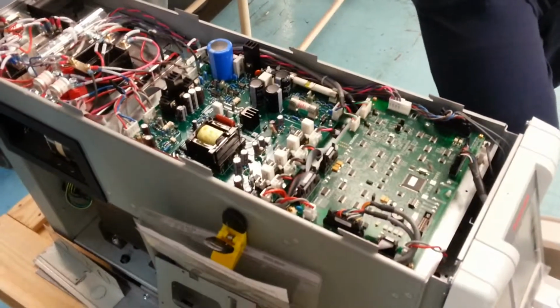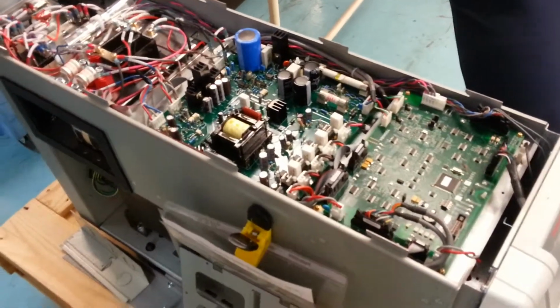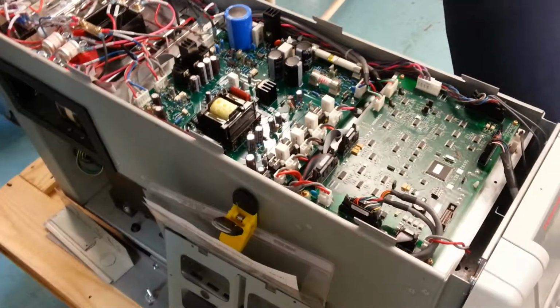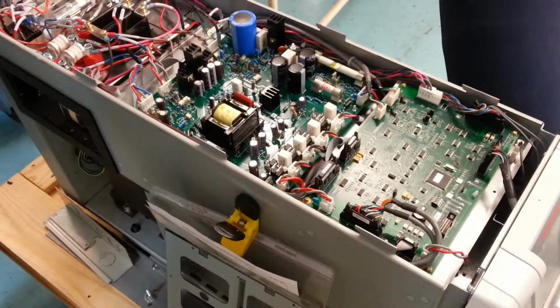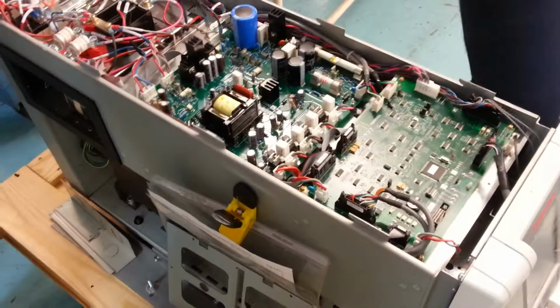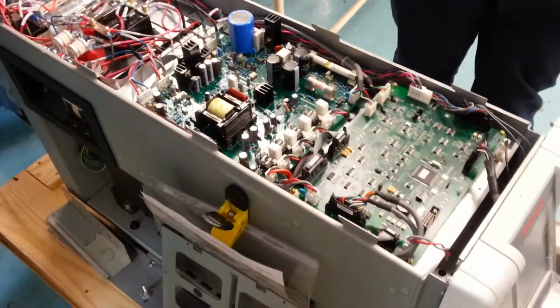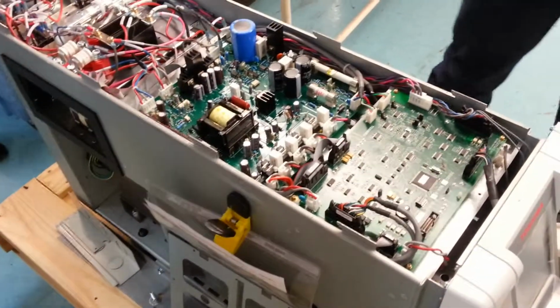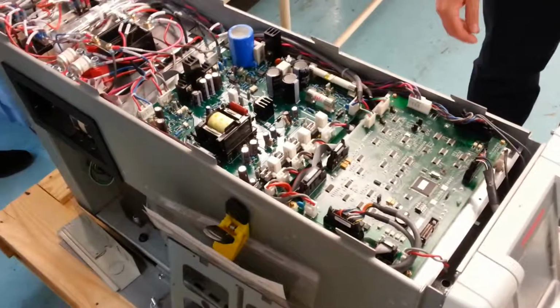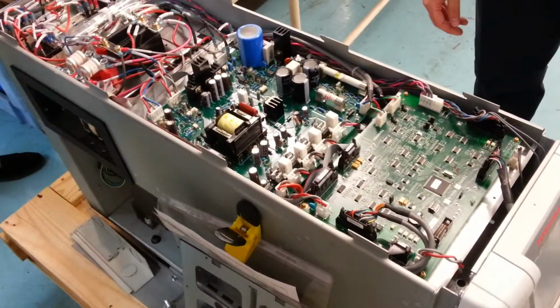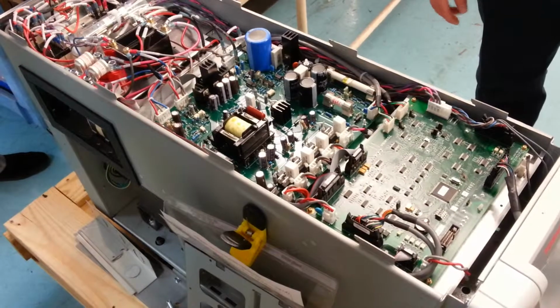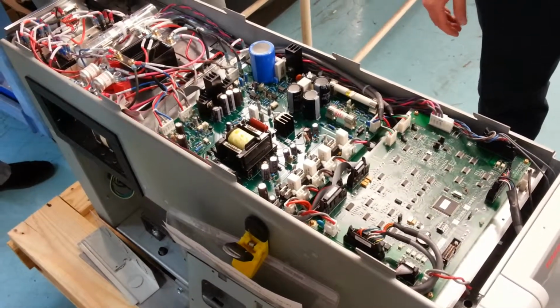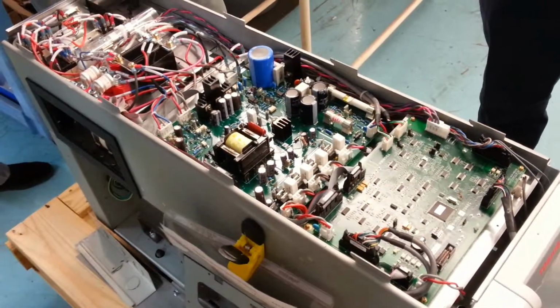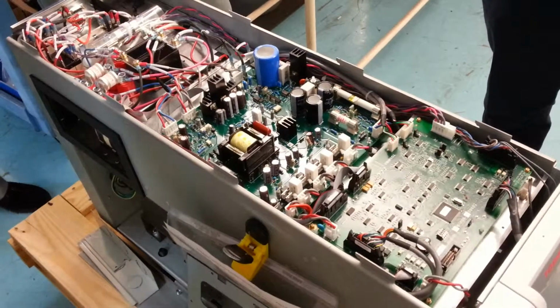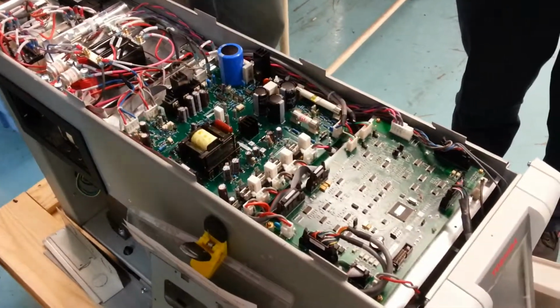But there's a point in the design of the board where the amount that can be drawn and the gain of the device have only a certain limit you can go. Then you'd have to redesign the board and redesign the software to handle that change in gain or feedback control. Most of the time on our units, though, the topology doesn't change. You may have to change the IGBT rating or the frequency at which it chops, in our case only about 7 kilohertz, or change the voltage reference.